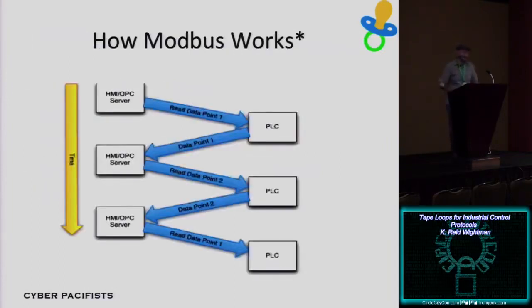So the way Modbus and the other protocols work, that's why the asterisk is there. This is pretty much how all the protocols work. You have a server, whether it's an OPC server or an HMI server, querying a PLC through time. It issues a request to the PLC and says, hey, what's the status of input 1? And maybe that's a temperature sensor for your beer mash.